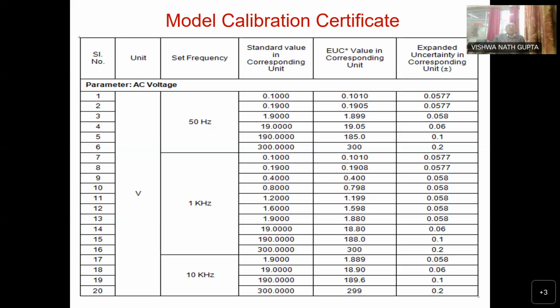Then after warming up, see sir, our calibration equipment also needs care like a baby or child, which means it should be warmed up properly. Zeroing should be done. What is zeroing, sir? Zeroing means any stray voltage, from the effect of a magnetic field or earth to neutral voltage, should be removed at least once in a week. And the temperature in the laboratory should be very proper.